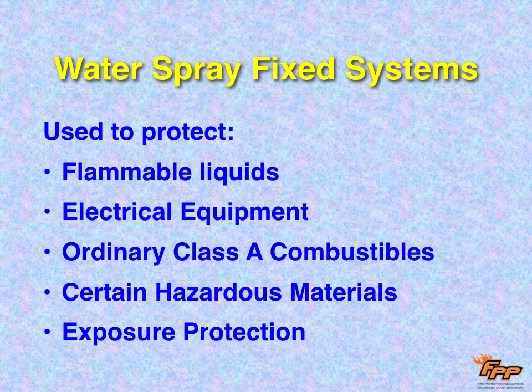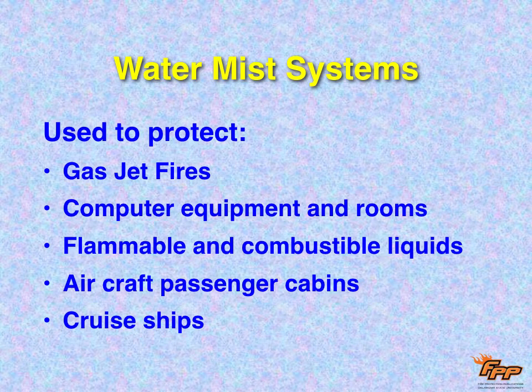Now, there's water spray systems, and the difference between water spray and sprinkler systems is just a smaller drop. They use these sometimes where there's hazardous materials or for electrical equipment where they don't want the equipment deluged with water, but they want a finer, mistier spray. In fact, the difference between sprinklers and water spray is the size of the drops. The difference between water spray and water mist is a much smaller drop.